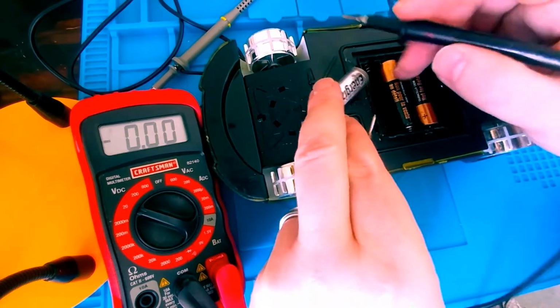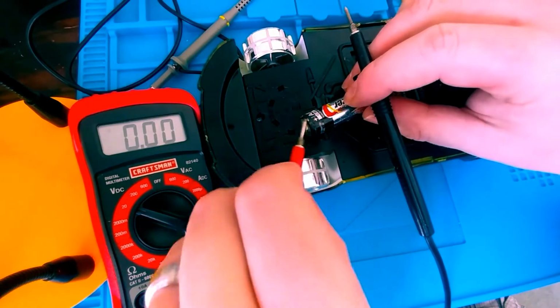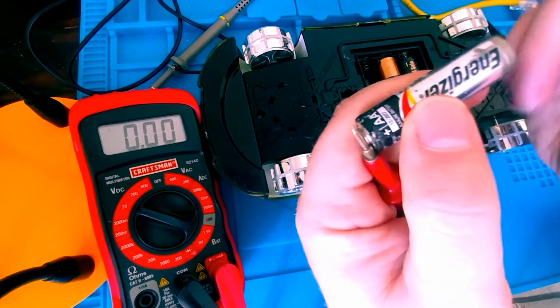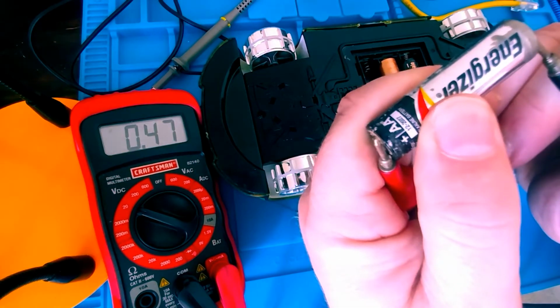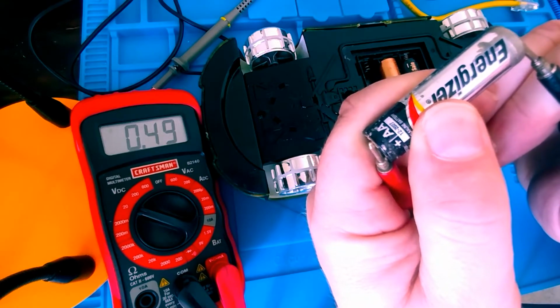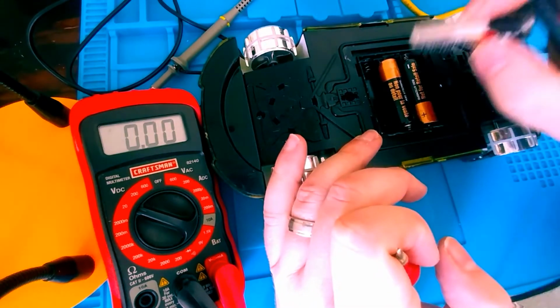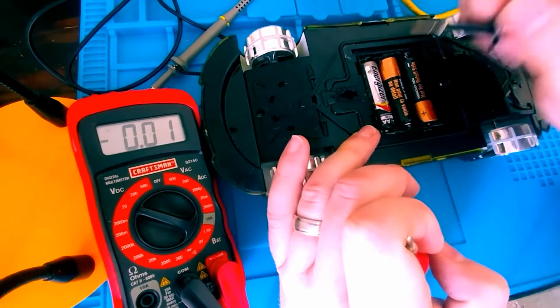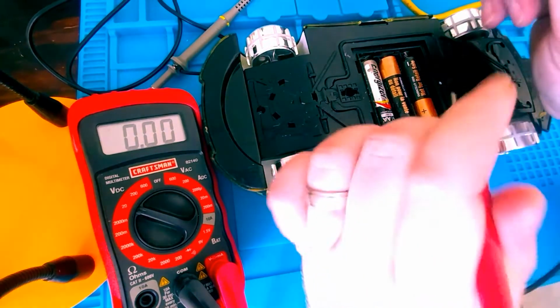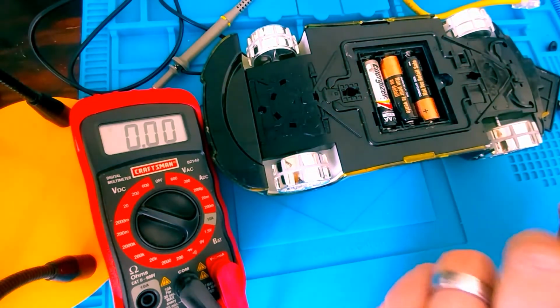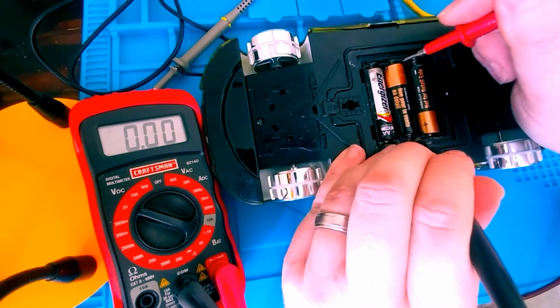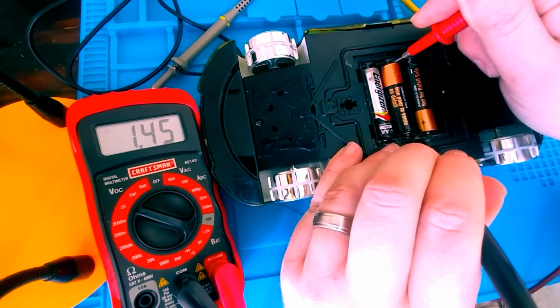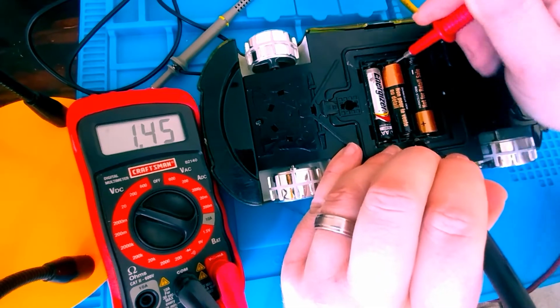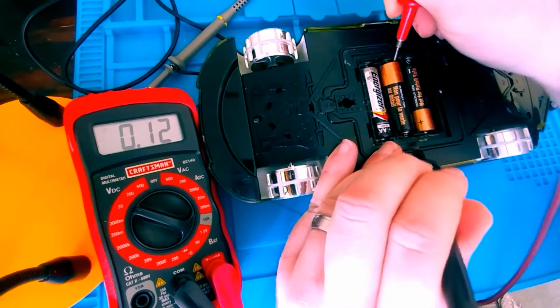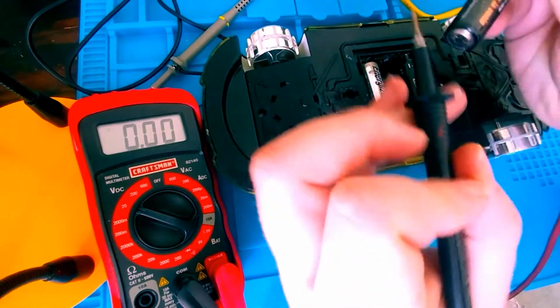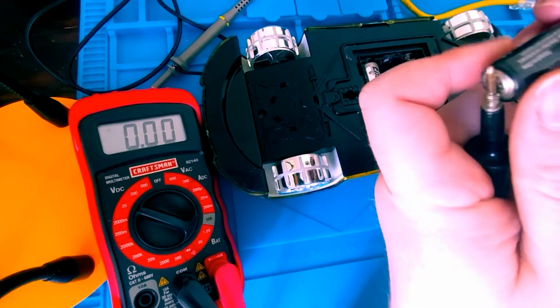If I pop the battery out and take a measurement from the positive terminal to the negative terminal, you can see that voltage varies a bit. But that battery is no good and will need to be replaced. This next battery, I suspect, is also no good and will need replacing. As a matter of fact, this is probably the only halfway decent battery — as I remove it from the circuit and measure it independently, we can see how much charge remains.